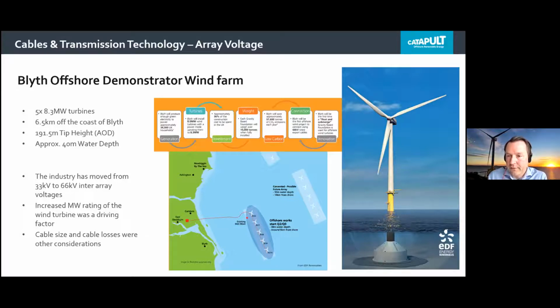But there's also an electrical first - where it says connection on the slide. Blyth was the first offshore wind project to connect using 66 kV export cables, one of the big recent moves in the electrical system in offshore wind. Previously, particularly in the inter-array of the turbines, 33 kV was the voltage many early wind farms used. But as turbines got bigger, that voltage didn't make sense anymore, so as the megawatts increased we wanted a higher voltage. This was particularly useful for keeping cable size more manageable and keeping cable losses under control. The beauty of the demonstration project is it gives stakeholders confidence that the technology works - they're not just seeing it on a simulation, they're seeing it working with real hardware.